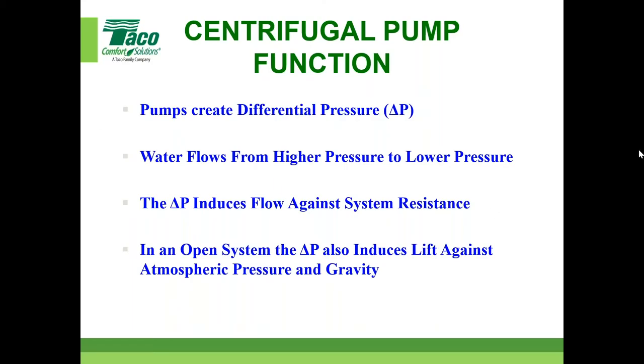So what does a pump do internally? It creates a differential pressure. So hopefully a lot of you, if not all of you, have thought about differential pressures in a hydronic system, heating or cooling, mostly heating or cooling. We're talking HVAC here. There's condenser water and heat pumps and whatnot, but either the building's got to be heated or cooled. That DP, that's what's being internally created inside this centrifugal pump, this rotodynamic pump, the circulator, the pump itself, whatever you want to call it. And water flows from higher pressure to lower pressure. That shouldn't make anybody upset, because it makes a lot of sense, right?